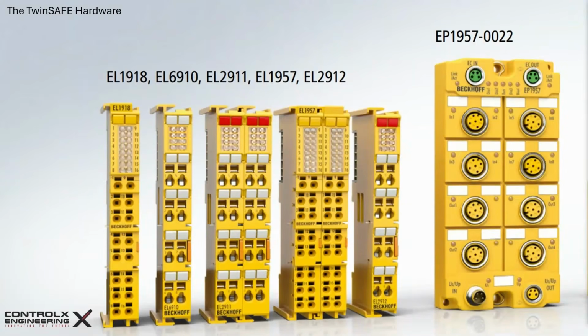That bright yellow housing is a global industry signal. It tells any technician opening the cabinet that this circuit is safety related. Do not bypass and do not treat it as standard I/O. But the real magic is on the inside.